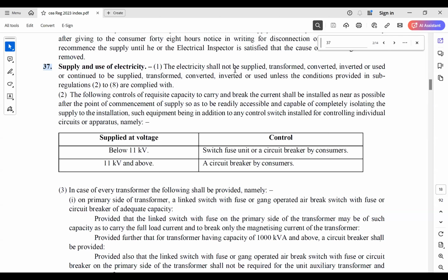So the same law, if I go to say Gujarat or Madhya Pradesh area, they have a mandate above 50 kilowatt you have to go for high tension supply. They don't have that kind of infrastructure network wherein they can provide LT supply at say 100 kW or say 150 kW.